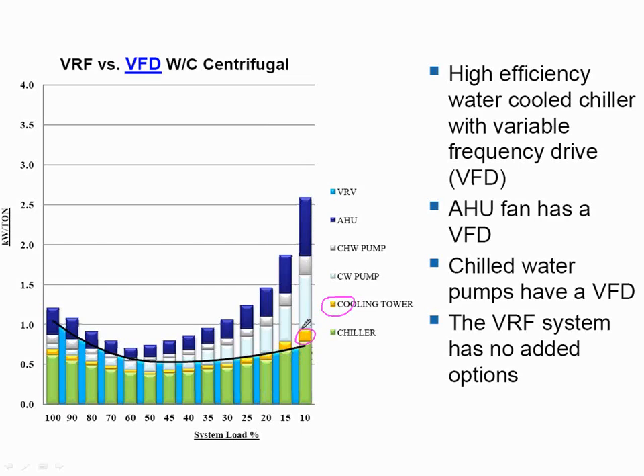So I get a pretty big yellow bar over here. Then I got to add in the chill water pumps and the condenser water pumps. That's this light blue and the silver bar. Then I got to add the fan energy in for the air handler, which are these blue bars, right? If I start doing that, now I'm comparing the top of this line to the black line. I'm not a good artist, sorry. Right? Now, in most cases, the VRF is going to win.